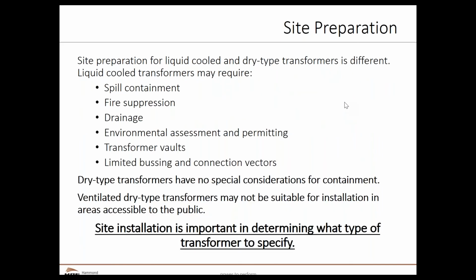Site preparation is a big one. With liquid filled transformers, there might be things like spill containment, fire suppression, drainage, environmental assessments and additional permitting, transformer vaults, limited bussing and connection vectors that will result in some differences in design that may not be any consideration or any issue for a dry type.